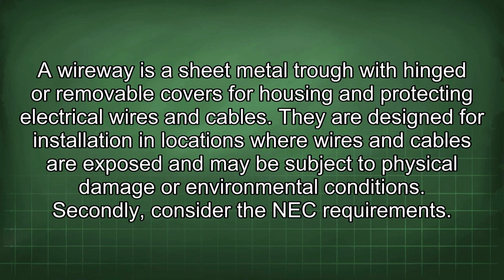A wireway is a sheet metal trough with hinged or removable covers for housing and protecting electrical wires and cables. They are designed for installation in locations where wires and cables are exposed and may be subject to physical damage or environmental conditions. Secondly, consider the NEC requirements.